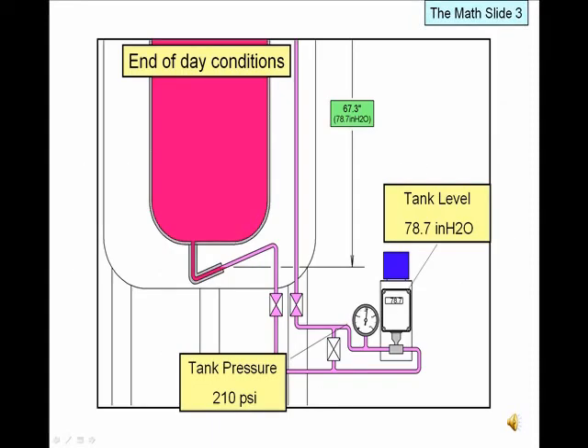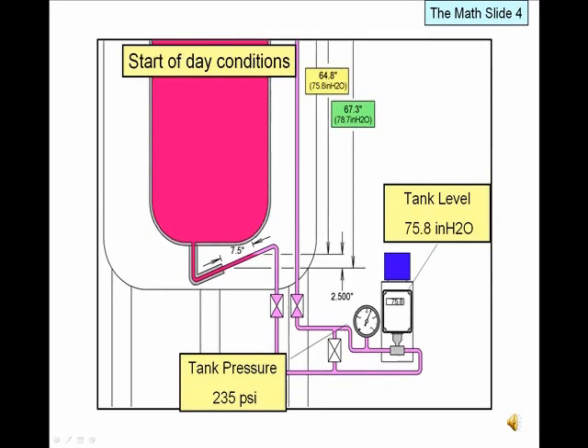To recap: the starting conditions, or the end of the day, had a tank pressure of 210 PSIG and an indicated level of 78.7 inches of water. The ending condition, or the start of the next day, saw pressure rise to 235 PSIG and the level drop to 75.8 inches of water. This drop was due to the level rising in the high phase line trap by 2.5 inches.